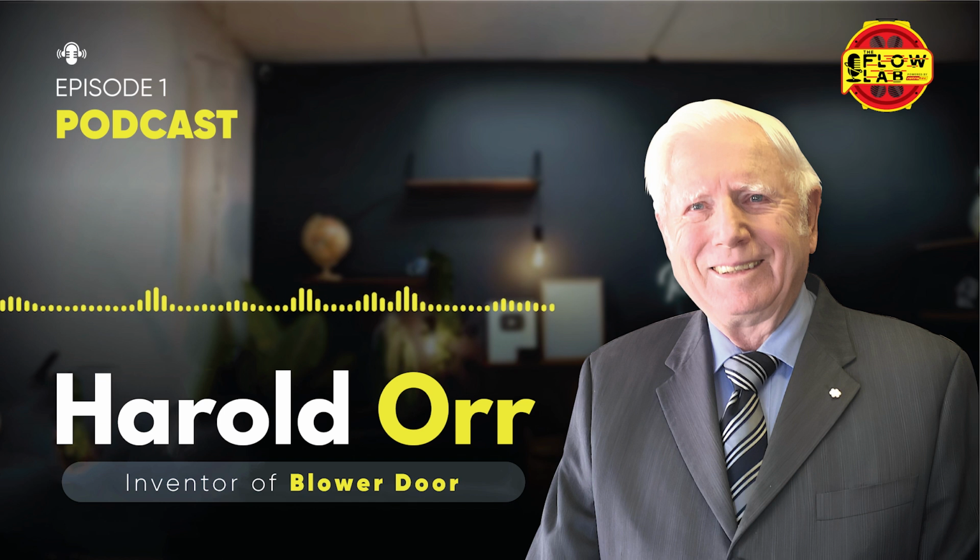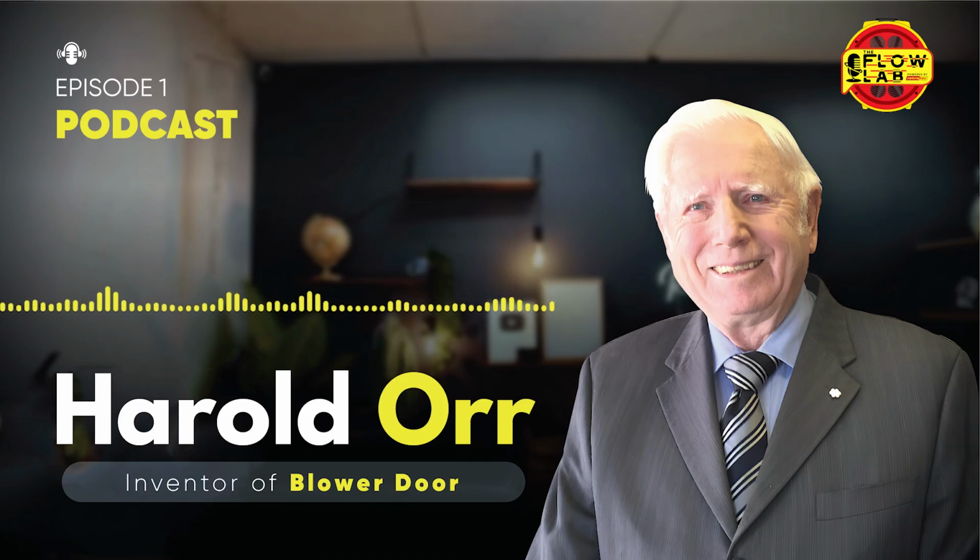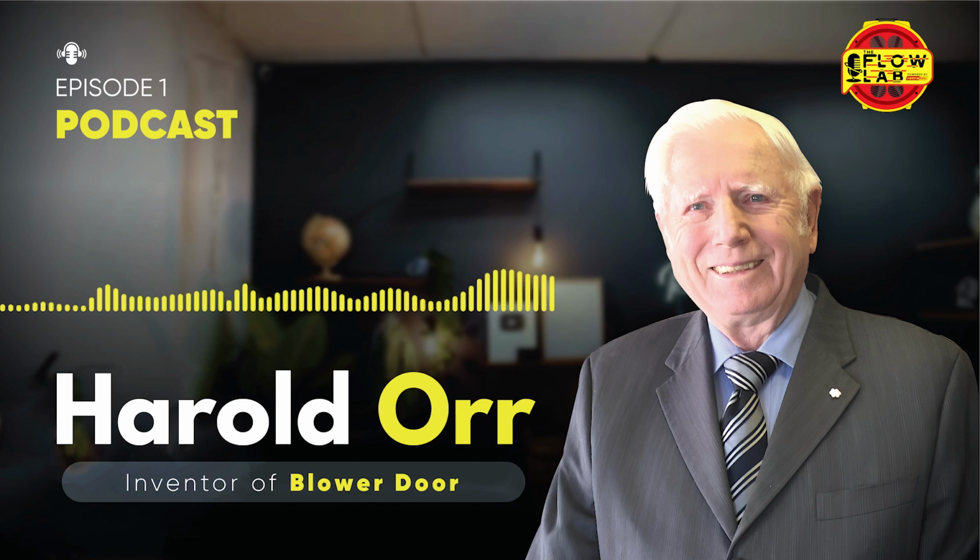And as a result of that, Dr. Feist, I forgot his name now, anyway, from Germany, came over and saw what we'd done, and they went back and started the Passive House movement in Europe, where if you build or renovate a building, you shall bring it to the Passive House standard, and they require 0.6 air changes per hour at 50 pascals. Not quite as good as we did, but pretty decent still, much better than normally done.